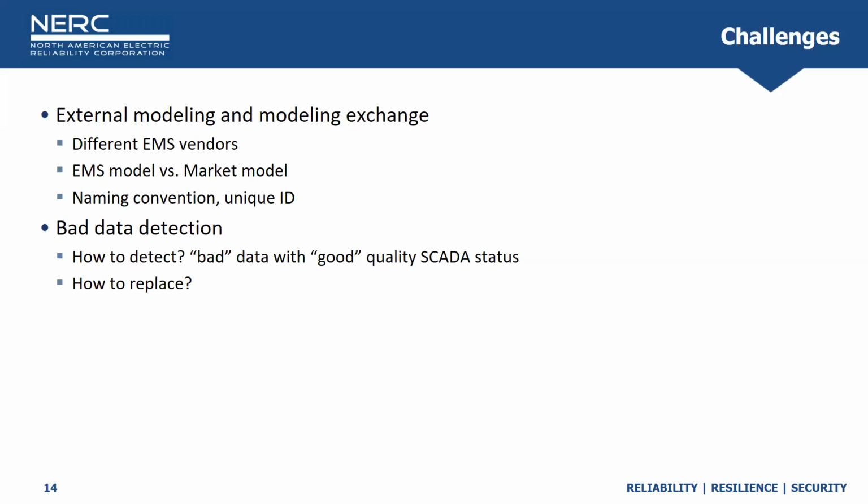The other thing is that we have multiple EMS vendors, but unfortunately one challenge is that the vendors use different models, because every vendor has its own modeling facility, like GE and Siemens, OSI. The model cannot be exchanged or used without an adapter. So for example, if I use a GE model and export it, the one using OSI cannot use that. So they have to use CIM to convert as the median layer for translation. However, a lot of information is lost in this translation.